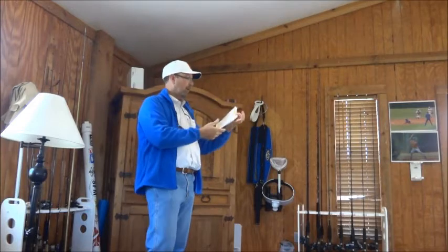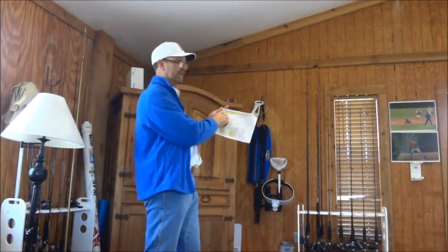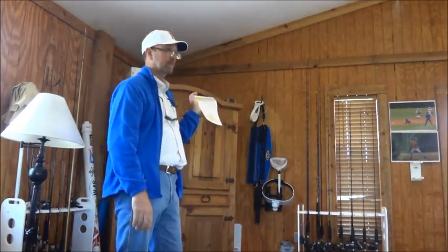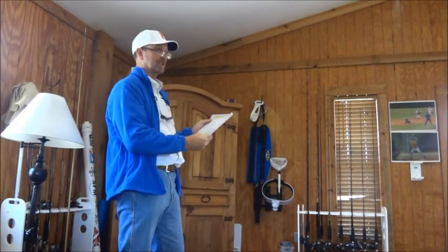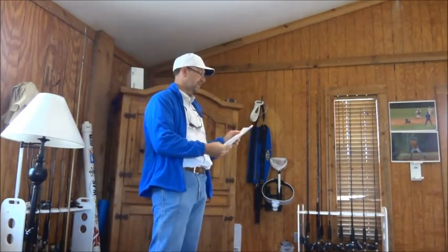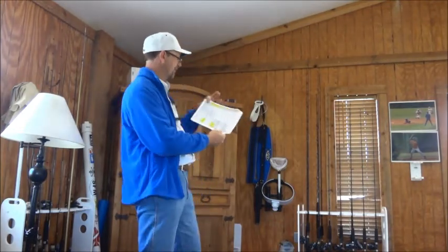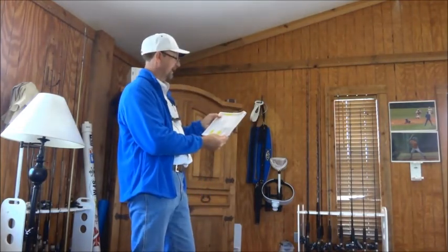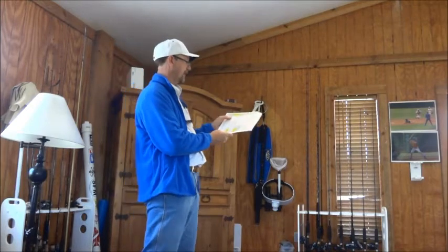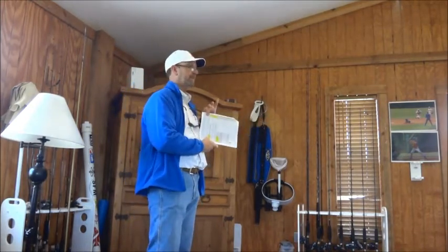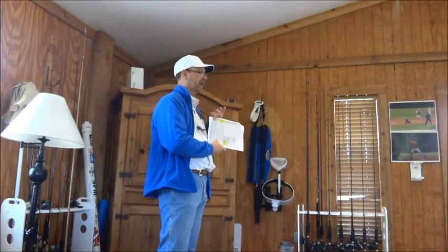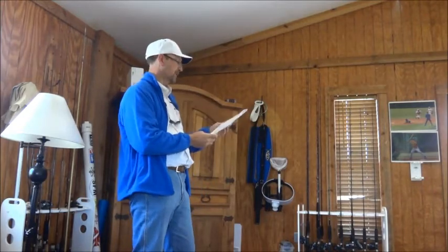We sum all wells to total gallons. Do you see that right there in the first column? So that's the total gallons that have been used for all the wells in a given month. You see the number of days in the month. We divide by the number of days and we get the gallons per day. That's your peak month right there. That's those blue bars that you just saw on that plot. That's how you get the blue bars.